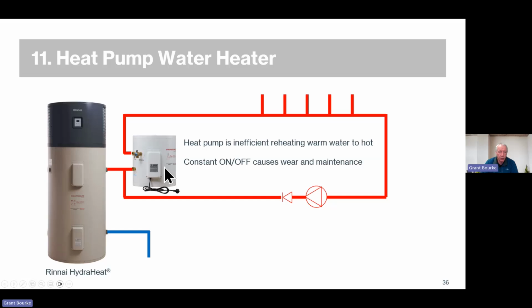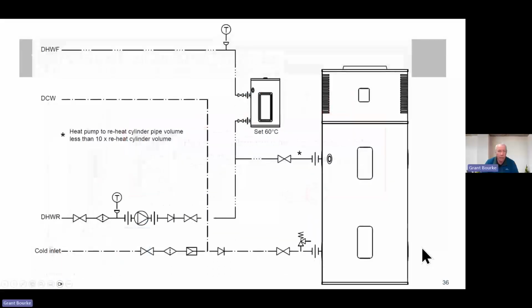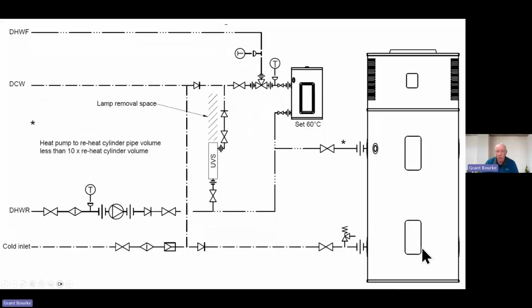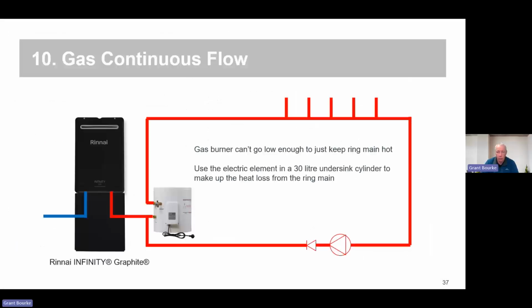And obviously the element in this needs to be big enough to overcome the heat loss out of the ring main. But if you do the installation as you saw before, that'll be no trouble at all. And then we've got a couple of sketches in the book how to do that for a high temperature and a low temperature ring main. Rinnai Infinity, same but for a different reason. The burner can't go low enough to keep the ring main hot, and the water heater will go on, off, on, off its whole life, and it won't last very long, and it'll give lots of problems.